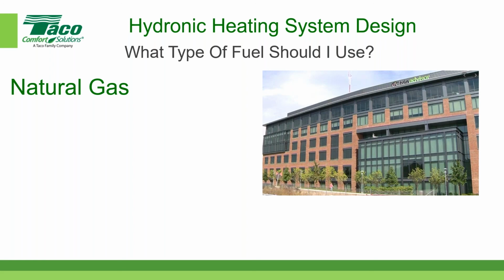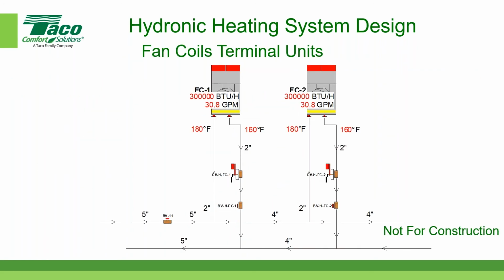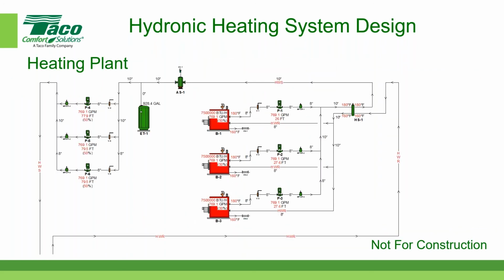Excellent answer. Can you go to one of your pictures of the detail piping, one of the detail ones showing the pumps? Yeah, scoot back one. So it's a little hard to see. Good question here. Can you have the air and dirt separator and an expansion tank on the primary side of your pumping system? Yes, you can. You could actually have two in there if you want, although in general, we only recommend one expansion tank because we only want one point of no pressure change in the system.